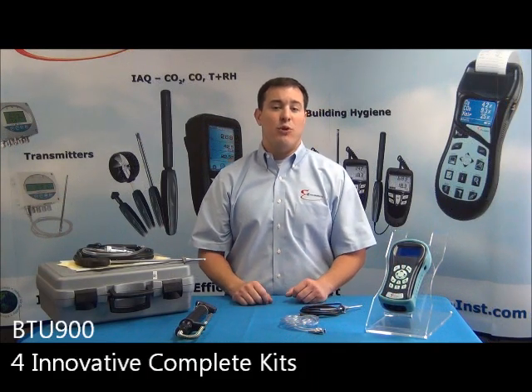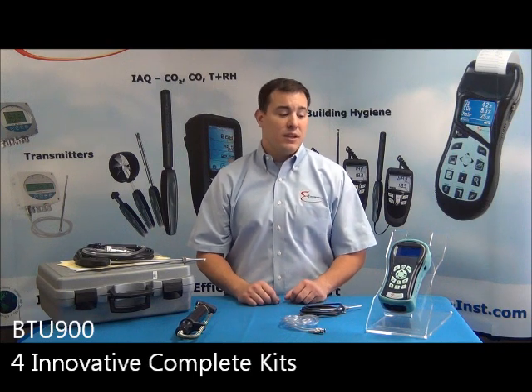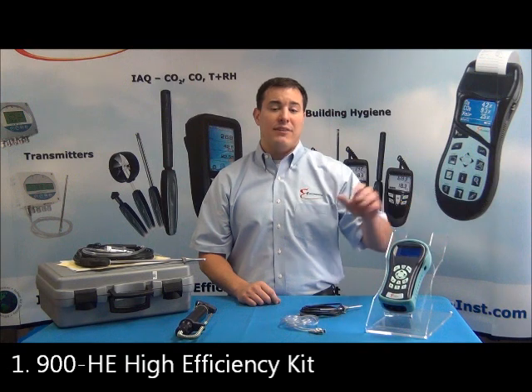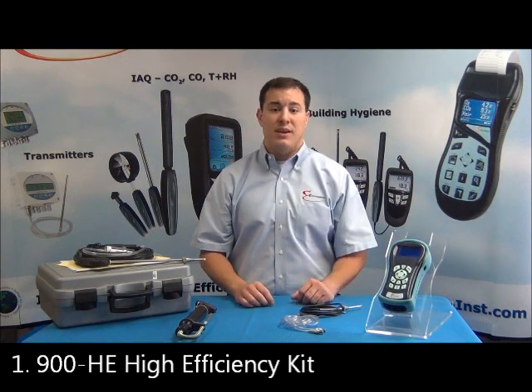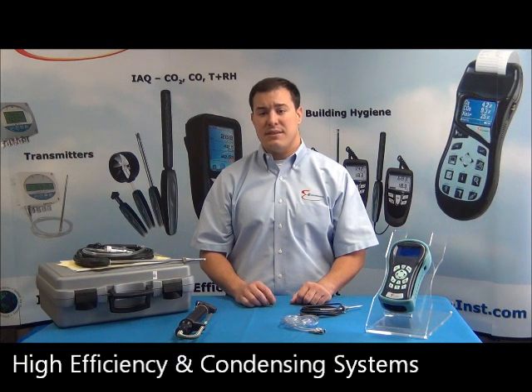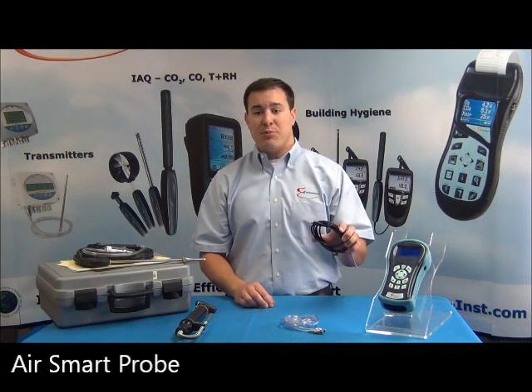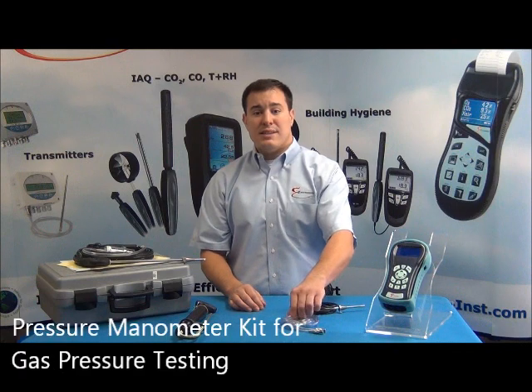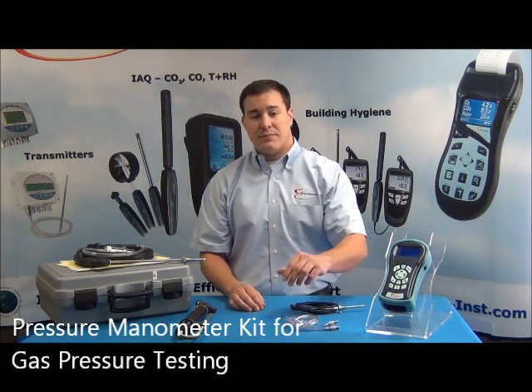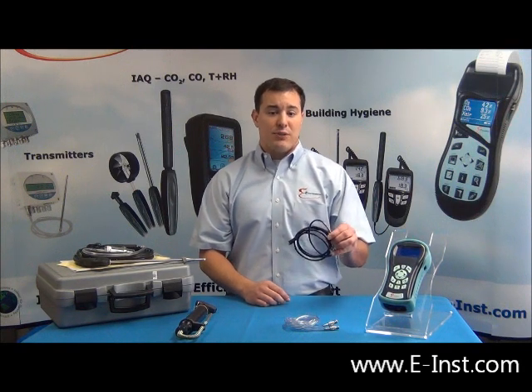The BTU900 comes in four innovative complete kits that we're going to cover. Number one, the 900 HE high efficiency kit comes complete with all of the smart probes and accessories you will need for high efficiency and condensing systems, including the Air Smart Probe. This is the probe that you will need to take the incoming air temperature measurements for forced air and condensing systems. Also included is the pressure manometer kit for all your gas pressure testing. As mentioned earlier, since combustion efficiency calculations are based on the differential temperatures, we need to take the temperature of the actual air being fed to the system and the flue gas temperature to properly calculate your true combustion efficiency. This probe is for condensing or forced air systems only and not needed for atmospheric boilers or furnaces.